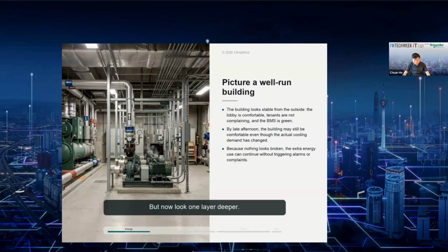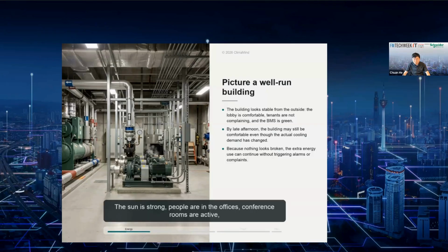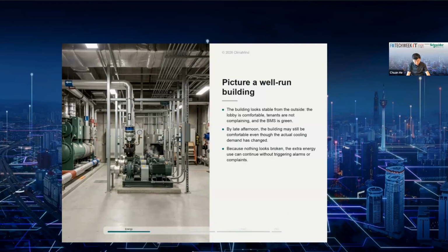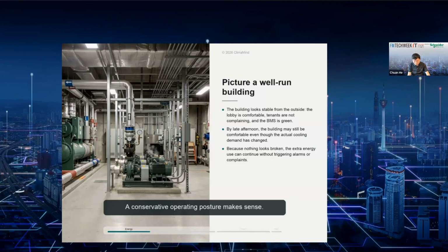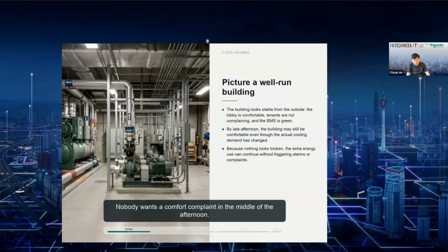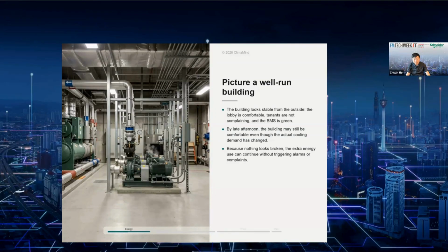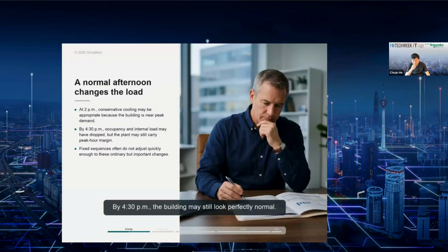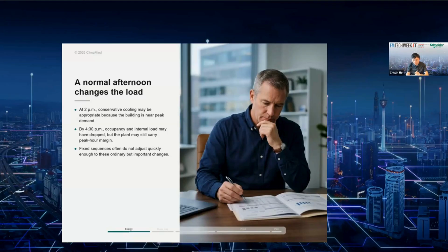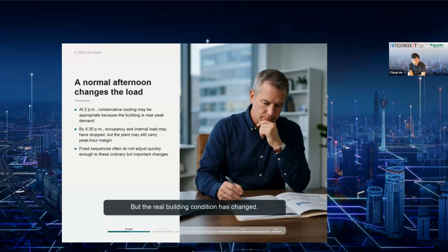But now look one layer deeper. At 2 p.m., the building is close to peak cooling demand. The sun is strong, people are in the offices, conference rooms are active, and the cooling plant is working hard. A conservative operating posture makes sense. The plant needs margin. Pumps need to move water. Nobody wants a comfort complaint in the middle of the afternoon. By 4:30 p.m., the building may still look perfectly normal. Temperatures are in range, no alarm is demanding attention. But the real building condition has changed.